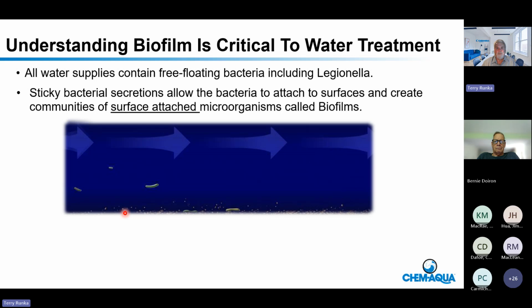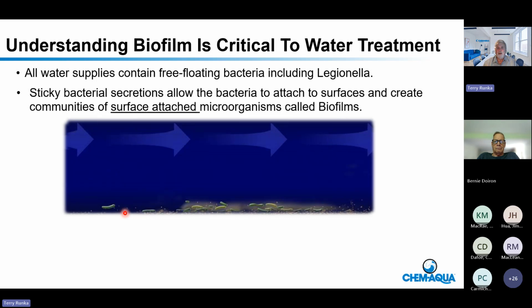Now, one last shot at the biofilm: where does it come from and how does it affect you? All water contains bacteria, good and bad. Some will hurt you, most won't, and it's live and it's in your water. Live things eat, and when they eat, they poop. The secretions from bacteria, especially Legionella bacteria, are a polysaccharide—a very gooey, sugary substance that will stick to little cracks in the substrate or drop out and stick on low flow or no flow areas.